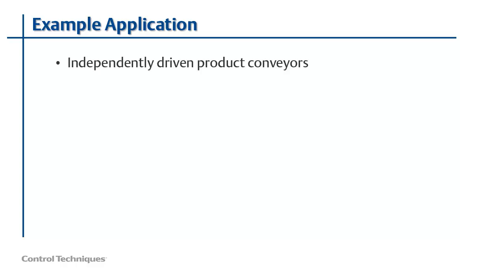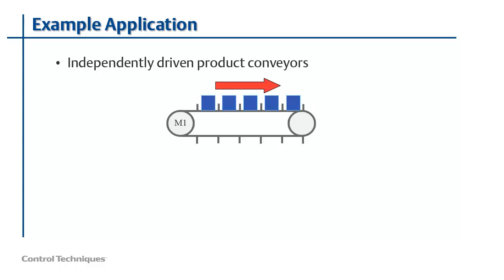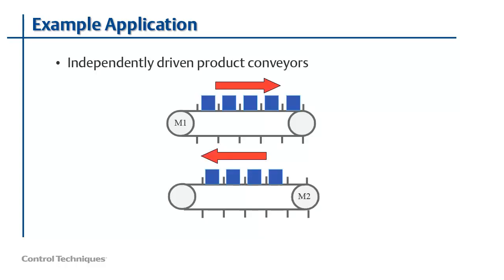To illustrate the use of Menu13, let's have a look at a typical application. A very common industrial control challenge is when there are two independently driven product conveyors that need to be synchronized together. The goal is to synchronize the two conveyors together such that the products on the top conveyor can be placed in between the lugs on the bottom conveyor. In this type of application, not only is it important that the speeds of the conveyors match, but also that the relative position of the lugs on the two conveyors line up as well. Let's see how we can solve this challenge using Menu13 in a Unidrive M700.